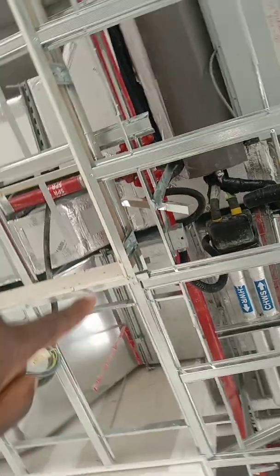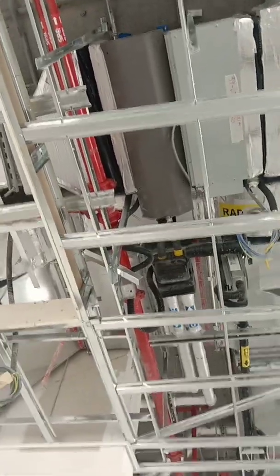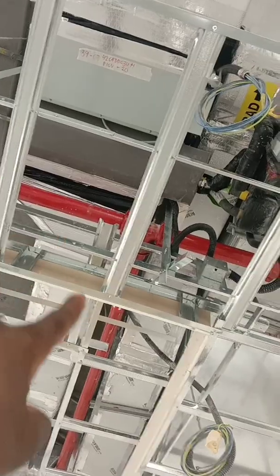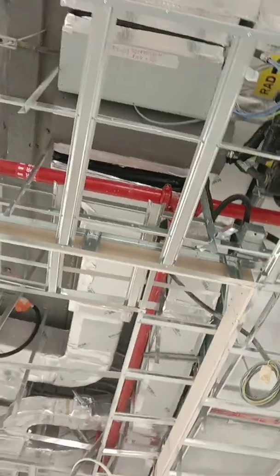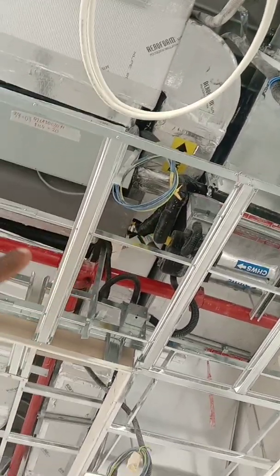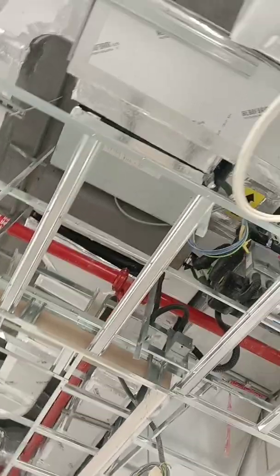On the valve package, we also have a control system — controlled by the BMS (Building Management System). We've done our cabling and conduitings, with a 3x3 box, flexible conduit and cable connected to the valve package of the FCU. That is done for the BMS as well as all connectivity to the FCU. We also need to give power to the FCU — we've installed the isolator unit with flexible conduits, cabling, and termination all completed. That part is also ready for civil ceiling closure.